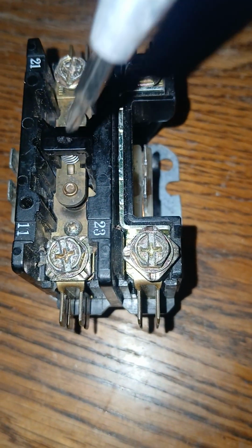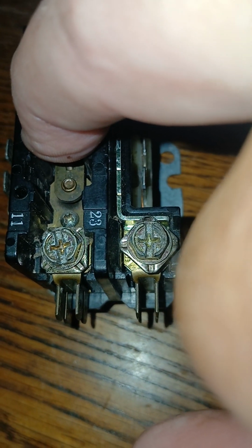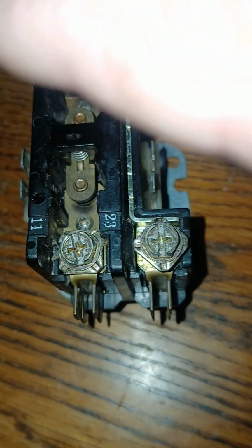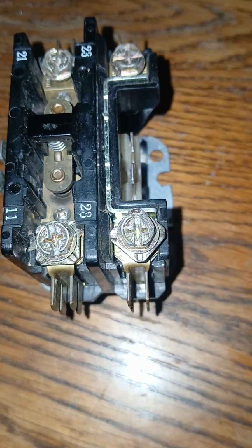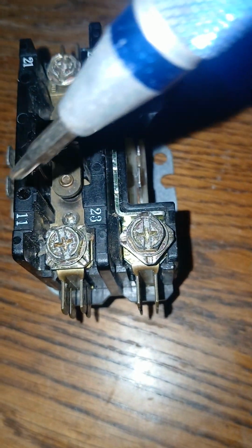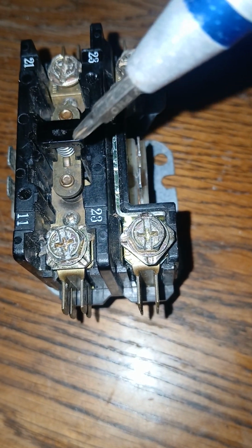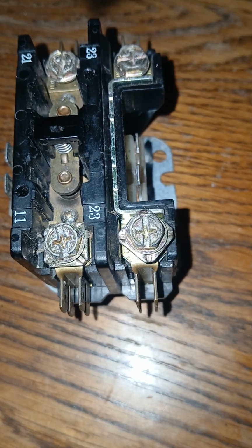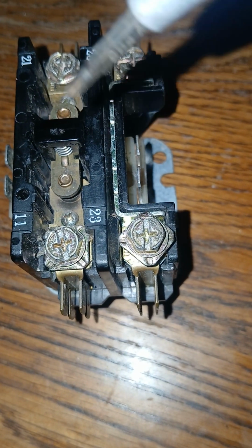But if these contacts are welded shut, this point and this point, meaning this is trapped in, and once the low voltage terminates, this still stays in. One needs to turn the electricity off to the system, whether that be quick disconnect or a breaker, and change the contactor. And one other tidbit of information: ants, for some reason, do like to perhaps congregate in these areas, and they can do something of that nature.